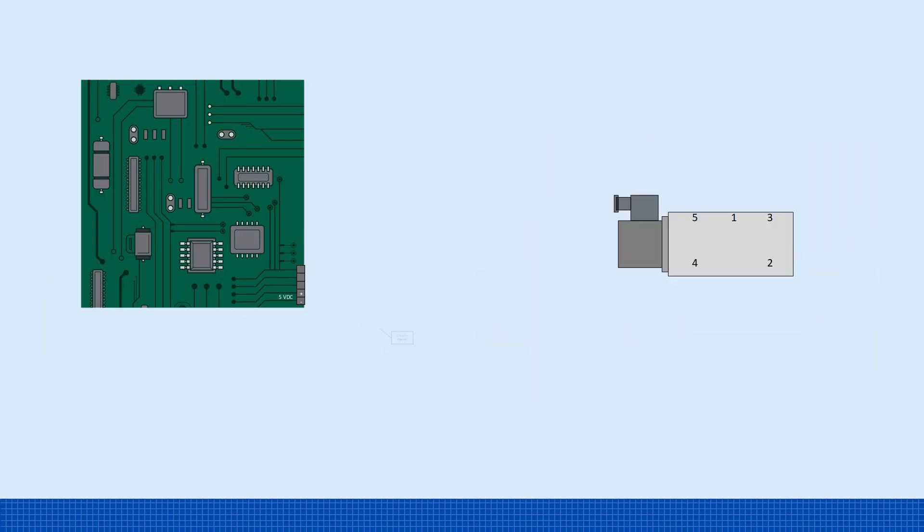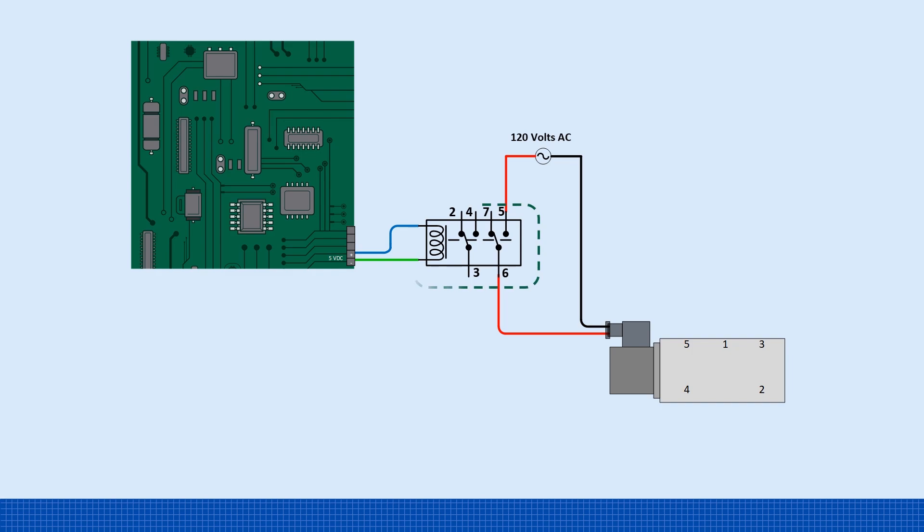So what is the third reason to use a relay? Let's say you have an electronic control card that only outputs 5 volts DC. That's not enough to directly power a 110-volt AC solenoid. But by using a relay with a 5-volt coil, the card can energize the relay. Then the relay's contacts, rated for higher voltage, can be used to switch the 110 volts to the solenoid.